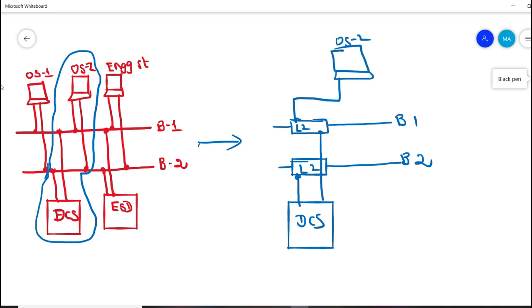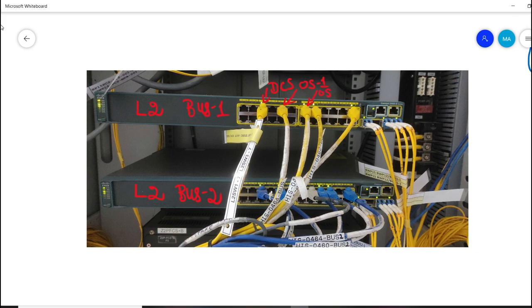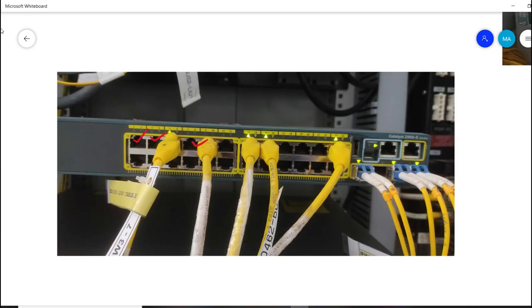So this is basically the L2 network switch. You can see we have two L2 switches: one would be installed in bus one and the other L2 switch would be installed in bus two. We have different ports where one port will be connecting to DCS and second port will be connecting to operation one, operation two, and so on. Similarly in bus two, the L2 switch again would be connecting control bus two network switches in DCS, operation one, operation two, and so on. You can see here we have around 24 number of ports in an L2 switch.